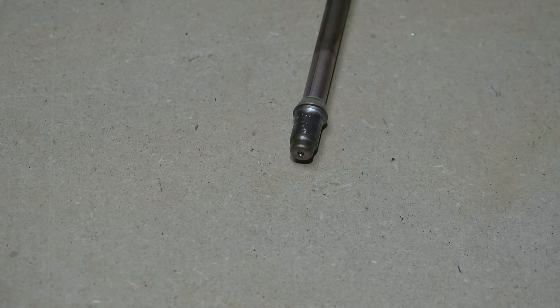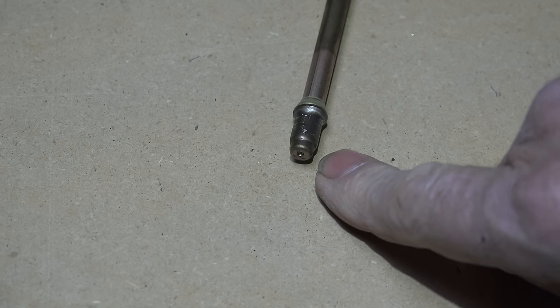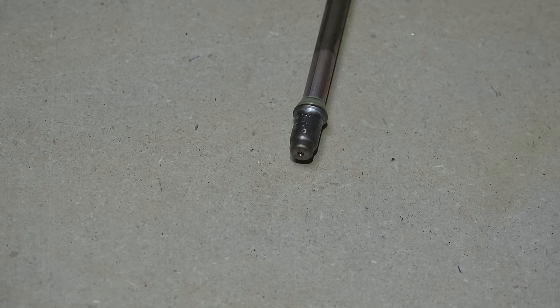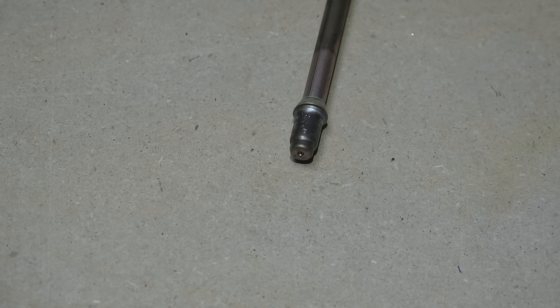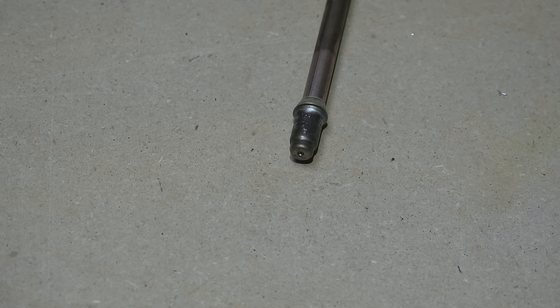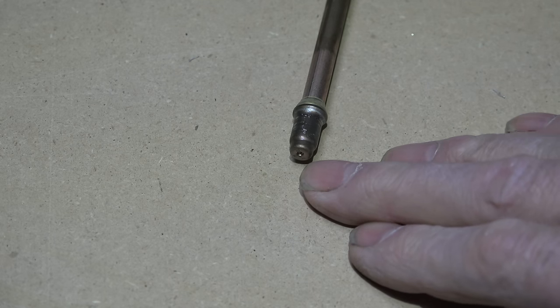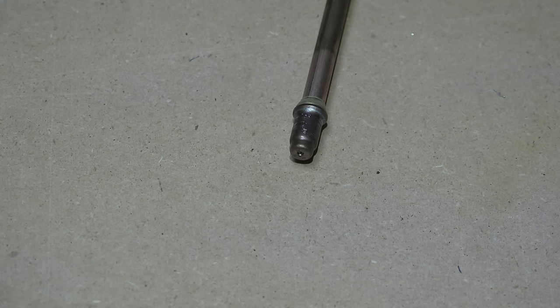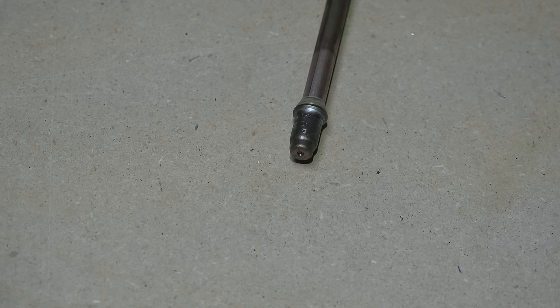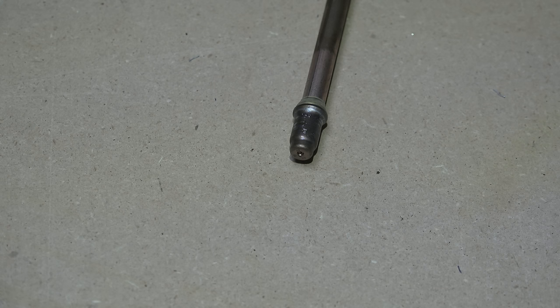But this small hole maintains a pressure in the tubing so that you've got your pressure, which is three and a half inches or whatever the manual says it should have - a water column pressure. And this restricts the flow so it does kind of spray out of there and it draws in the primary air that I was just showing you.